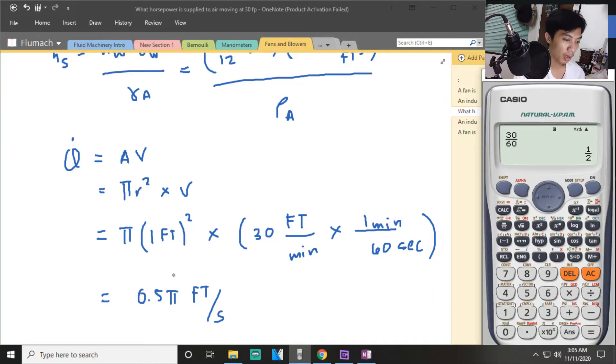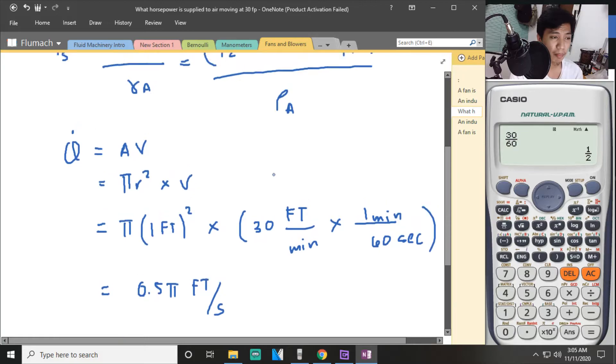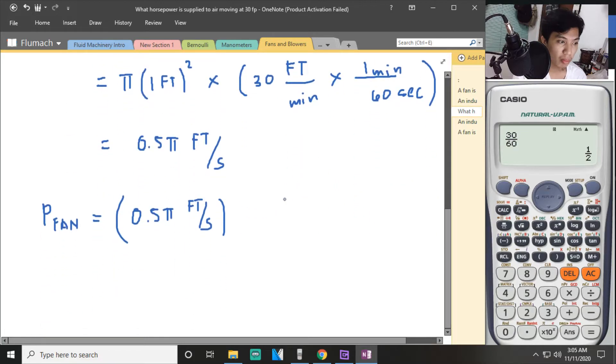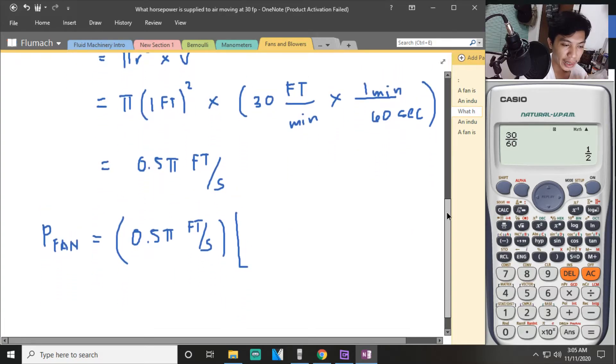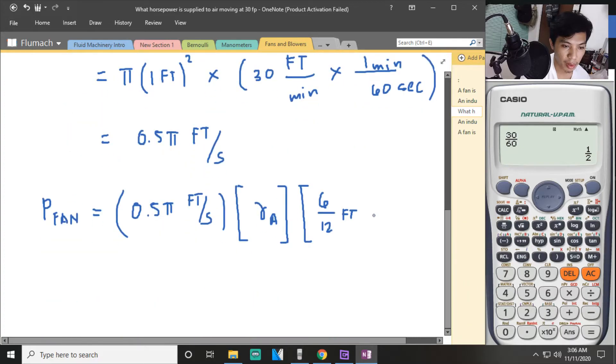Now you can solve for the power of the fan. So Q first, 0.5 pi feet per second. Sometimes I prefer minute because it's easier to remember the conversion. Then density of air. Then multiply by the static head. So that is 6 over 12 feet times 62.4 pounds per cubic feet.